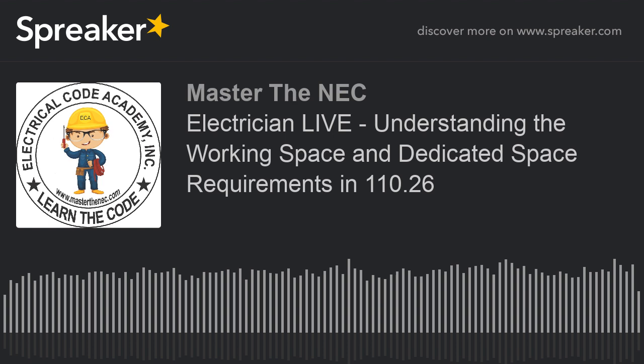So you might be able to kill the bus, but it is live, so there are live parts. So again, you're meeting the general rules of 110.26(A), so yes, this is going to apply. So then we look at condition number 1. And condition number 1 says, exposed live parts on one side of the working space and no live or grounded parts on the other side of the working space, or exposed live parts on both sides of the working space that are effectively guarded by insulating material.